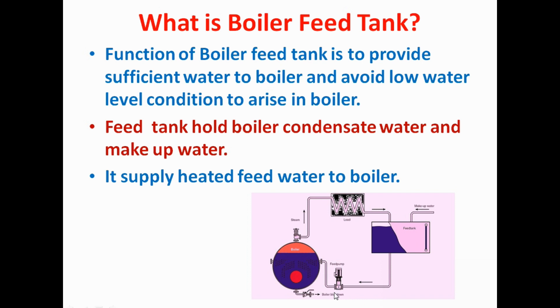Generally this water is hot because condensate water is coming into this tank. If we supply hot water to the boiler, boiler efficiency increases — because for every six degree rise in feed water temperature, fuel consumption reduces by one percent. This is a thumb rule. This is the function of the feed water tank.